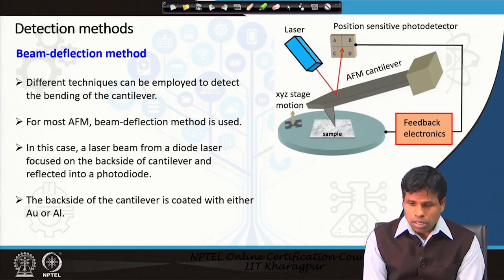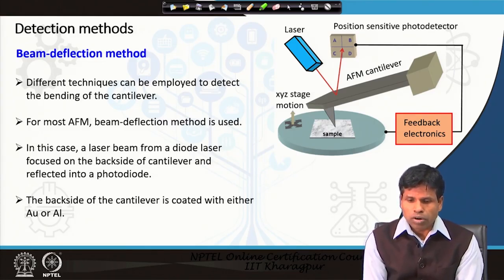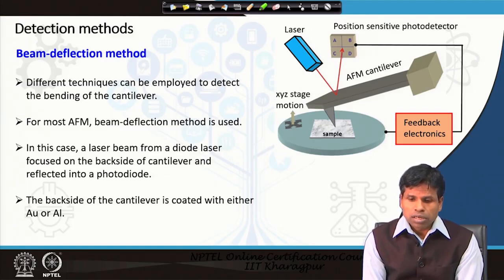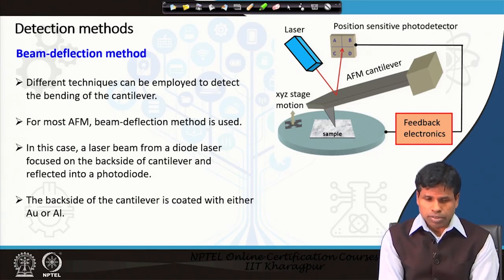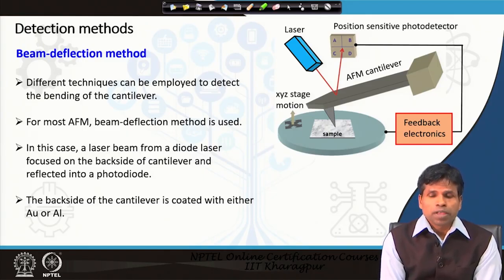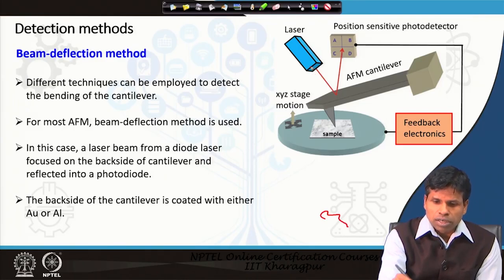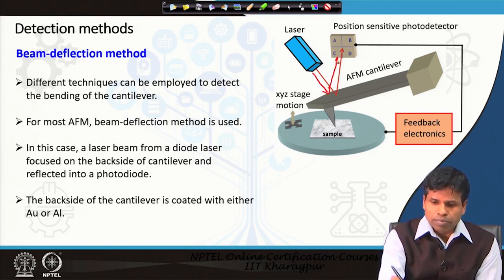Let us begin with the simplest AFM schematic. We have a sample over which there is an AFM cantilever that will scan over the surface. The deflection of the cantilever is detected by putting a laser beam on the backside of the cantilever, and the reflected laser light goes to a position-sensitive detector.